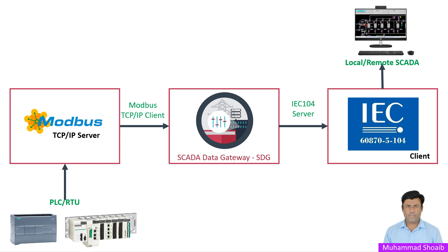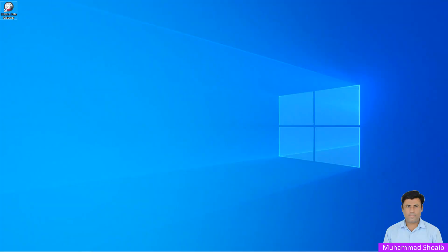In this setup, our RTU will work as a Modbus TCP server, and the SCADA Data Gateway will work as a Modbus TCP client. It will fetch data from the RTU, PLC, or DCS system. On the other end, our SCADA Data Gateway works as an IEC 104 server, and our SCADA system will work as an IEC 104 client. Let's see how we can configure the SCADA Data Gateway for this use case.